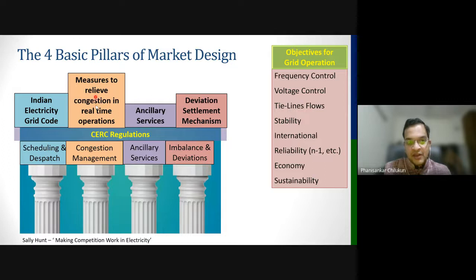After we have done all this, even then in real time, that means a few seconds before or during the exact time of day, there can be a deficit between load and generation. Then what to do, because these things are planned a priori? In real time we still have to do frequency control and voltage control, and control the tie line flows, and maintain stability.